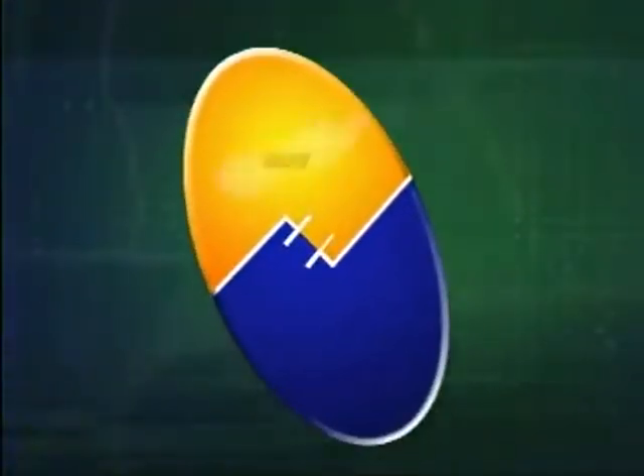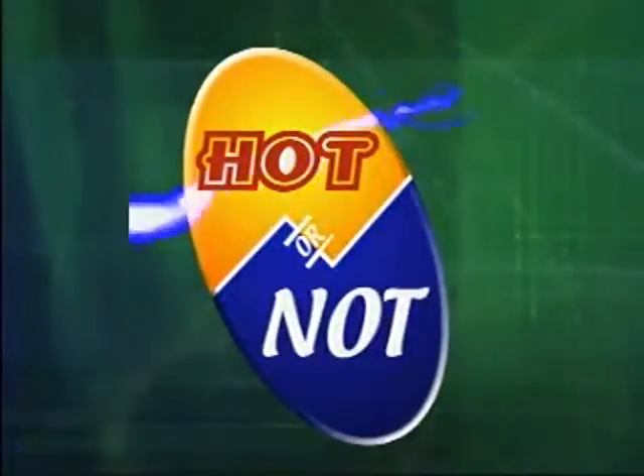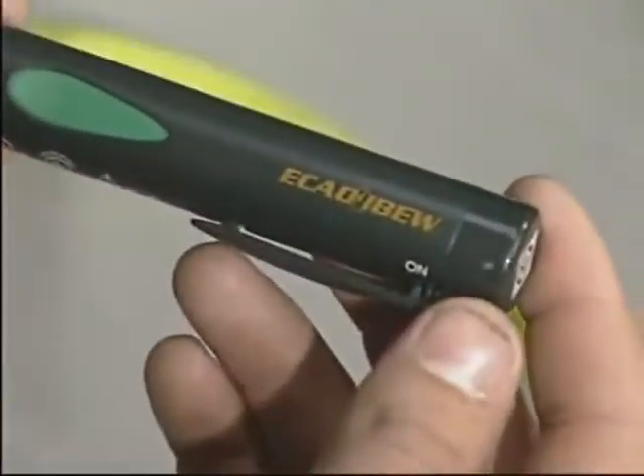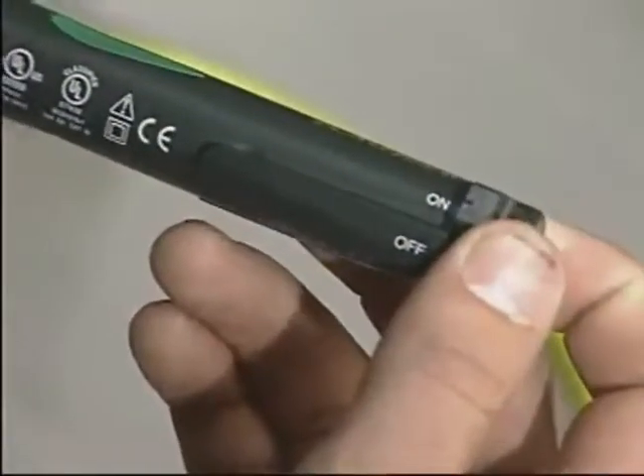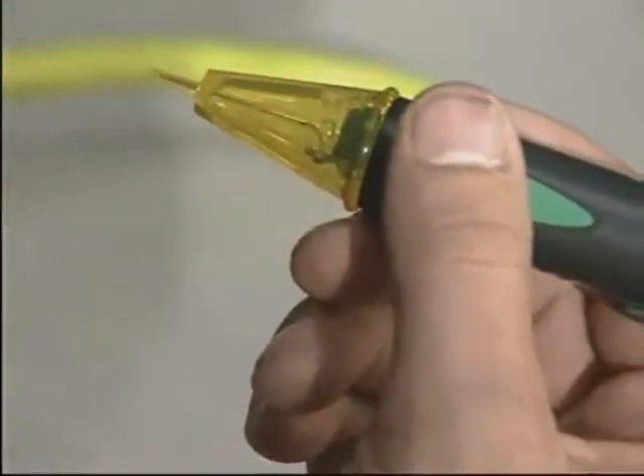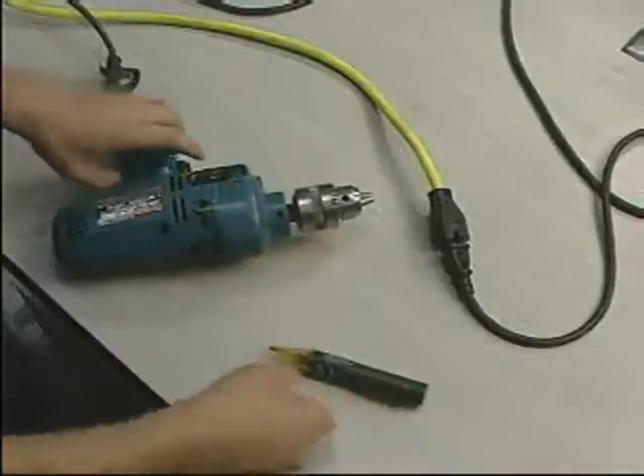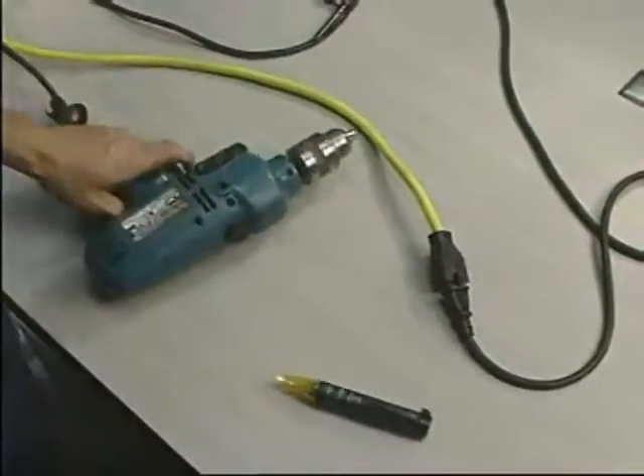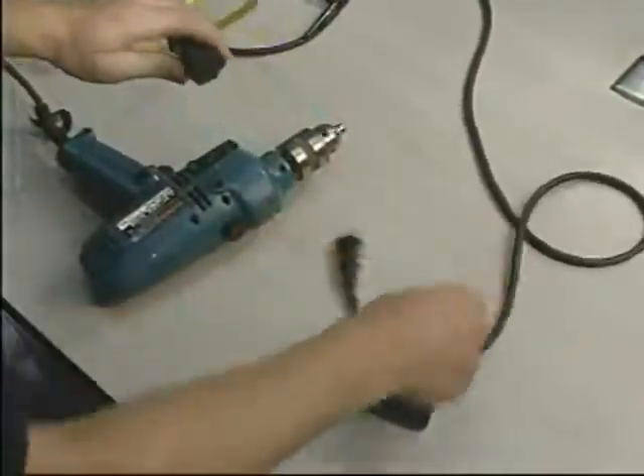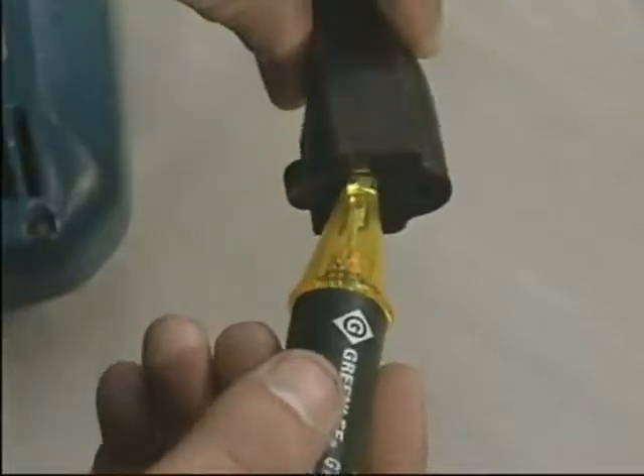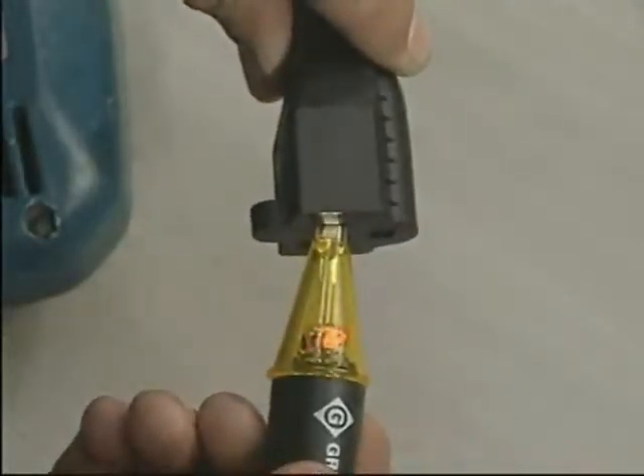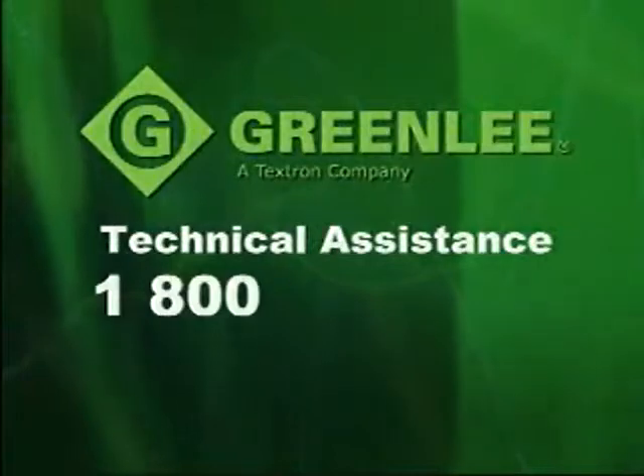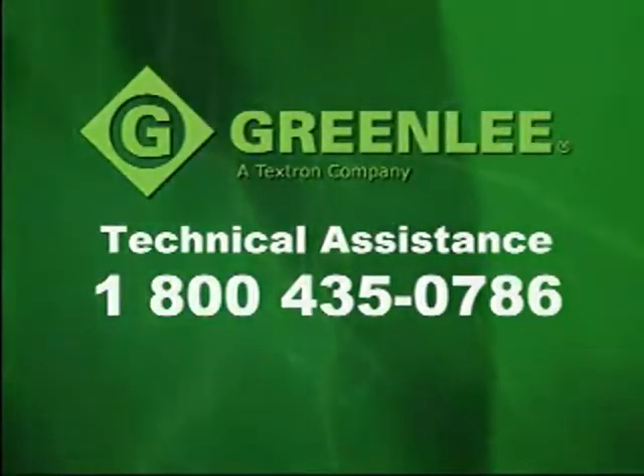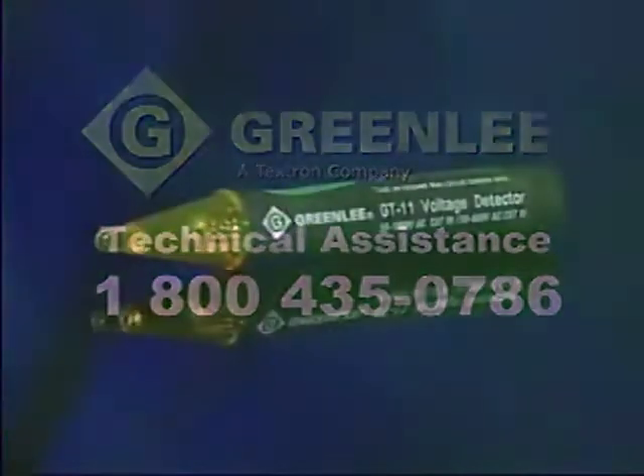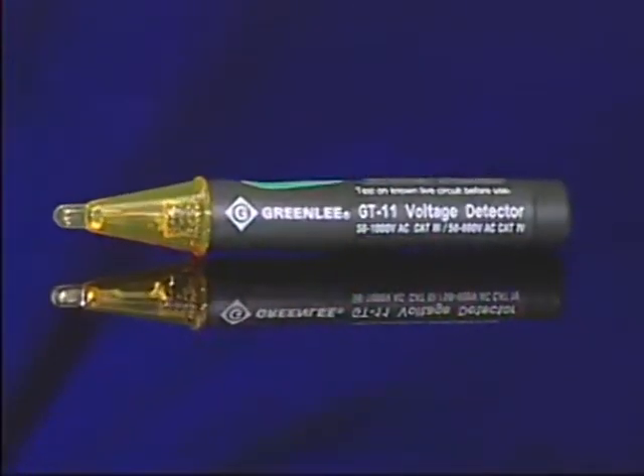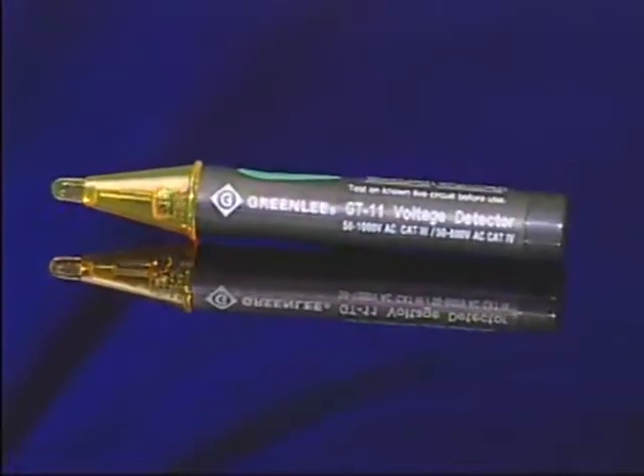Now it's time to find out, is it hot or not? Turn the cap clockwise so the pointer is in the on position. The first step is to test the unit on a known live circuit before each use. If the unit does not function, replace the batteries and check it again. If the unit still doesn't function properly, contact Greenlee Technical Assistance at 800-435-0786. Now that you know the unit is functioning, you can use it to test for the presence of voltage.